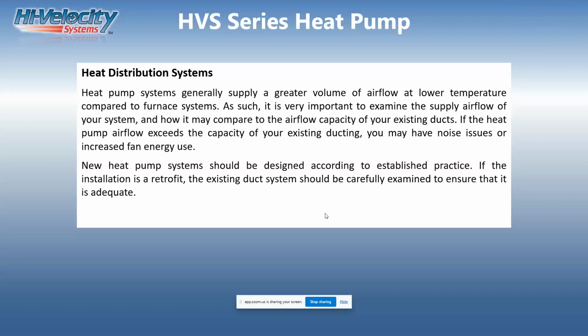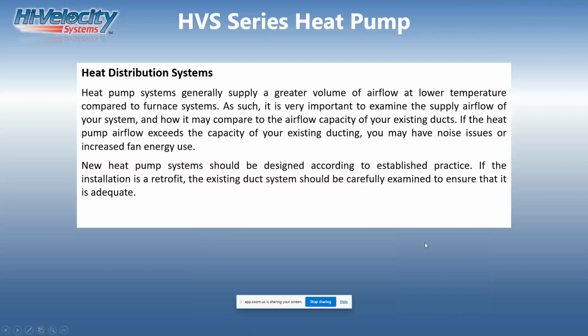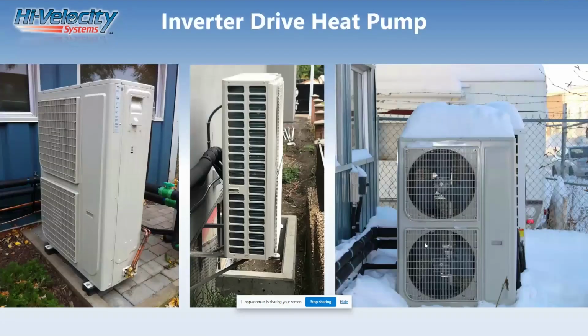New heat pump systems should be designed according to established practices. Apologize for that, no idea why. If the installation is a retrofit, the existing ductwork should be carefully examined to ensure that it's adequate. So really important to understand that.